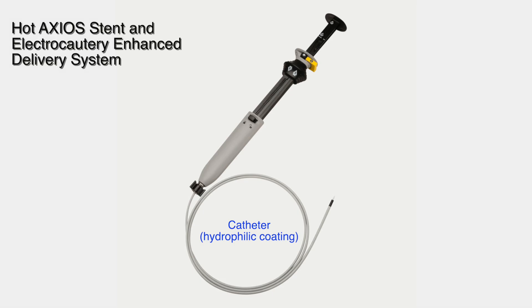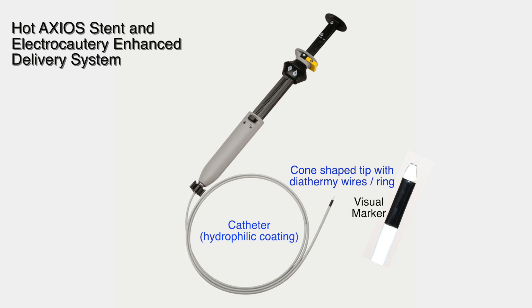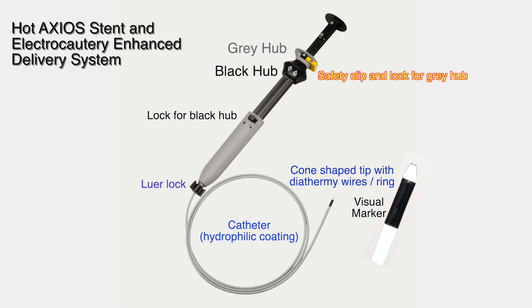A word or two about the hot Axios stent and electrocautery enhanced delivery system. The device comprises a handle and a catheter which has a hydrophilic coating. The tip of the catheter is cone shaped and has two diathermy wires running longitudinally along the slope of the cone and attaching to a tiny metal ring at the very tip. There is a short black portion of catheter proximal to the nose cone which acts as a visual marker. The catheter is wetted and passed down the channel of the echo endoscope. A Luer lock is used to connect the device securely to the scope. After the device has been luer locked into place the handle can still be rotated. The handle has a black hub and a grey hub situated midway up the handle. There is a lock switch for the black hub and a yellow safety clip and a lock switch for the grey hub.